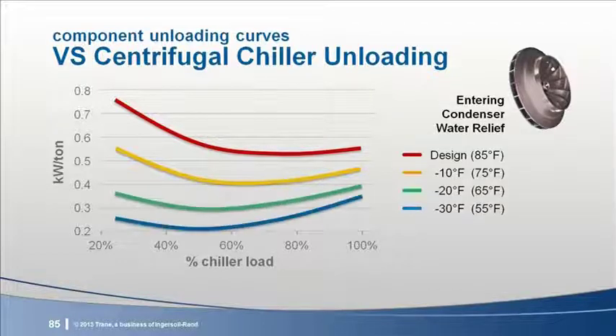20 and 30 degrees cooler condenser water enables even better chiller efficiency, as shown by the green and blue lines, although at a slightly lower incremental savings per degree cooler water. It should be noted that constant speed chillers' efficiencies benefit from cooler condenser water as well, just not as dramatically. What do these unloading curves imply about sequencing multiple chillers?